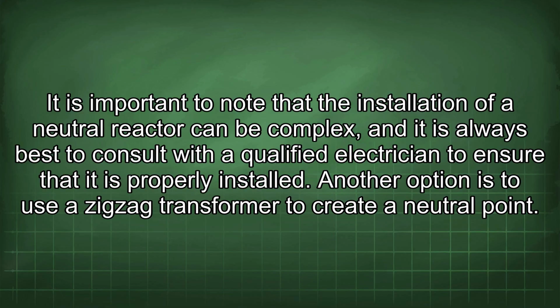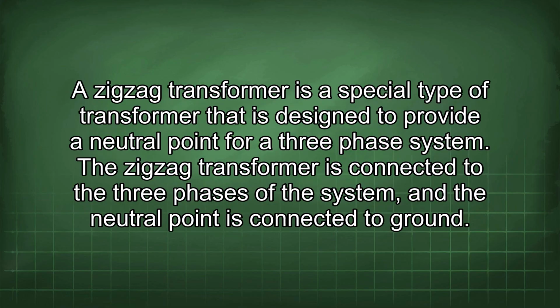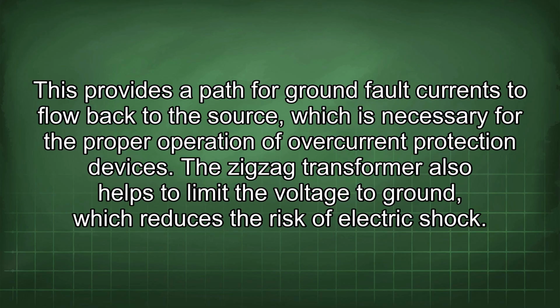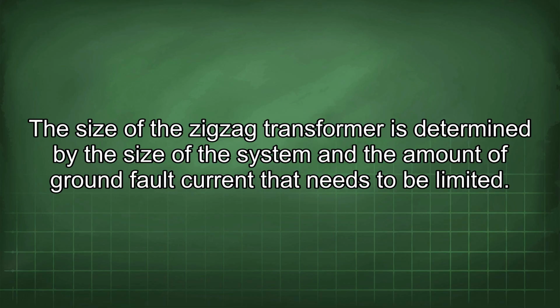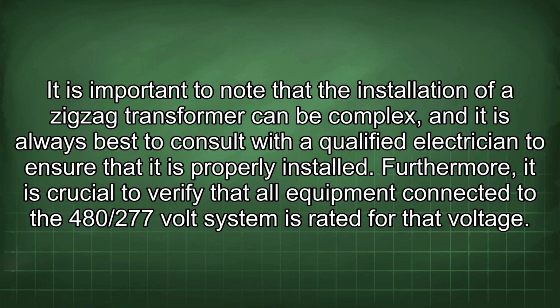Another option is to use a zigzag transformer to create a neutral point. A zigzag transformer is a special type of transformer that is designed to provide a neutral point for a three-phase system. The zigzag transformer is connected to the three phases of the system, and the neutral point is connected to ground. This provides a path for ground fault currents to flow back to the source, which is necessary for the proper operation of overcurrent protection devices. The zigzag transformer also helps to limit the voltage to ground, which reduces the risk of electric shock. The size of the zigzag transformer is determined by the size of the system and the amount of ground fault current that needs to be limited. It is important to note that the installation of a zigzag transformer can be complex, and it is always best to consult with a qualified electrician to ensure that it is properly installed.